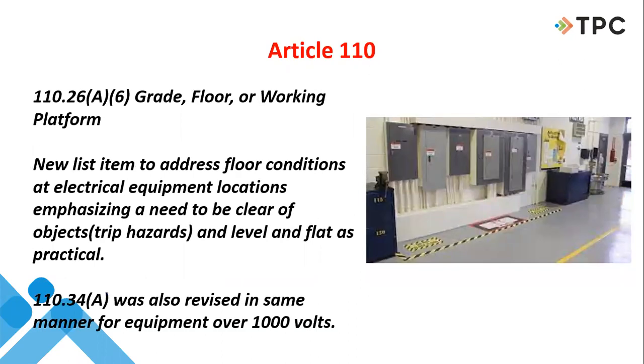Another issue, quite often, the floor around electrical equipment, in situations like in the photograph and so many other examples, is to be clear of trip hazards, objects lying around. The area should be level and flat as practical. One of the primary things that I've seen as an example here, I think in one of the latest photos, they had something a lot like this. And I think it was in a parking garage. And of course, you had the concrete parking blocks right there, 3 feet out from the wall where these panels are located. Well, talk about a trip hazard. That's what they're talking about, things like this.